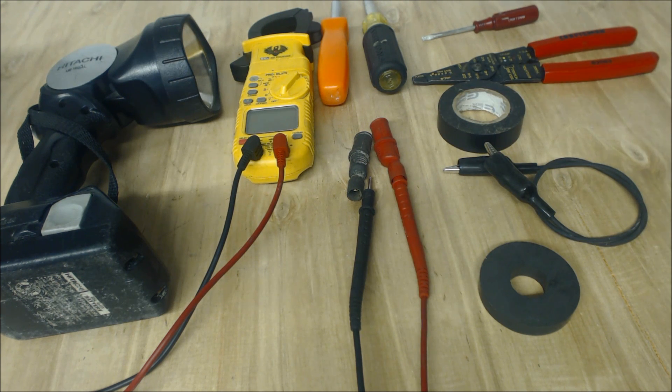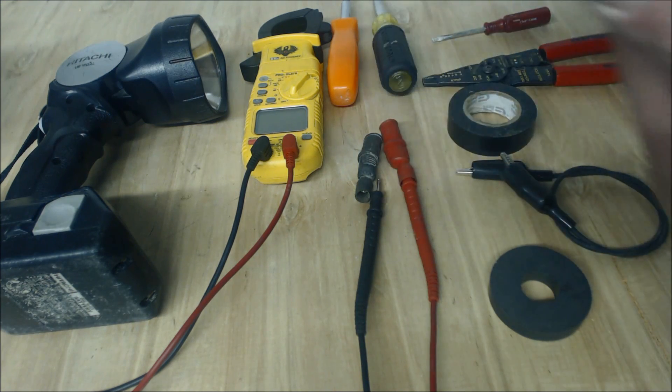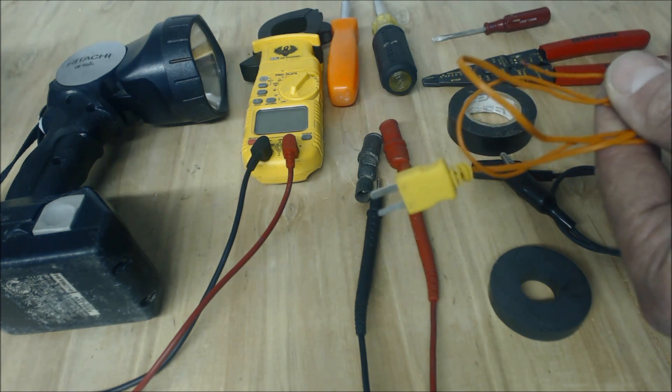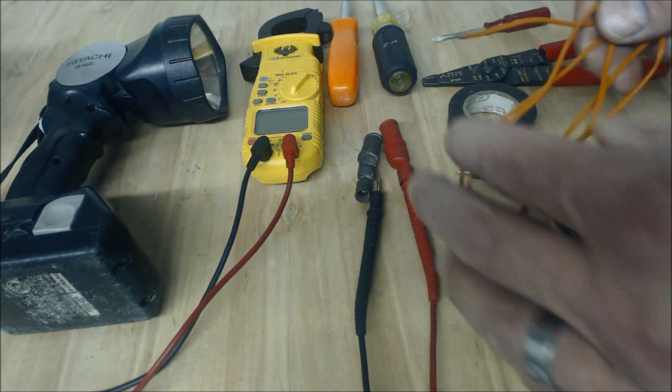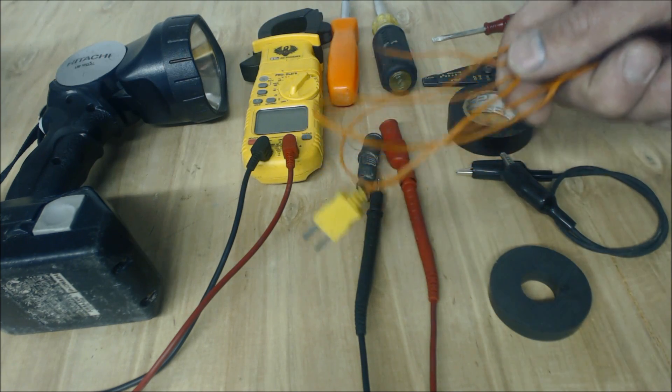Depending on what the customer says, say they say the cooling is working but it's just not getting cold in the house, obviously I might start with a temp sensor as well and a multimeter just to check my temp difference between the return and supply, or if it's heating I can do a temp rise.